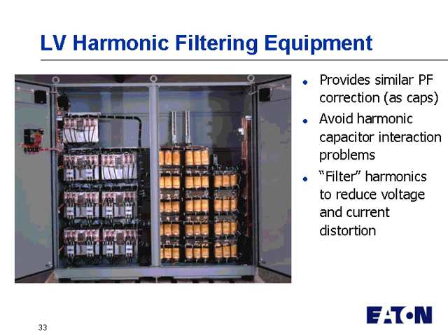This section shows low voltage harmonic filtering equipment, and again, this provides very similar power factor correction as a capacitor bank would, but it also avoids harmonic and capacitor interaction problems, and it may be used to filter out some harmonics that are bad on the system to reduce voltage distortion, for example.